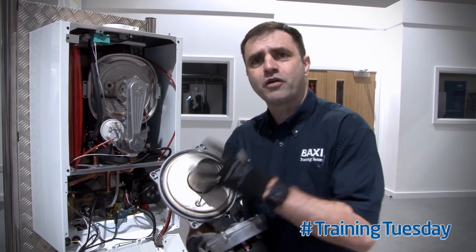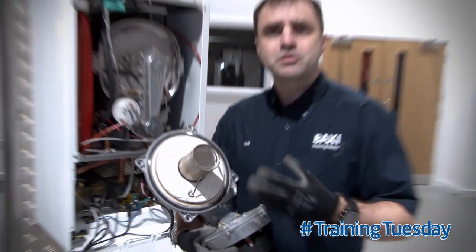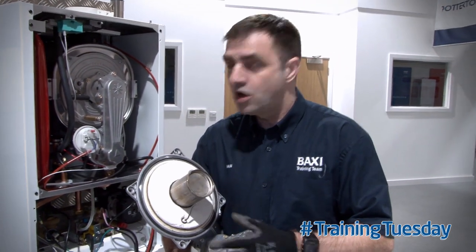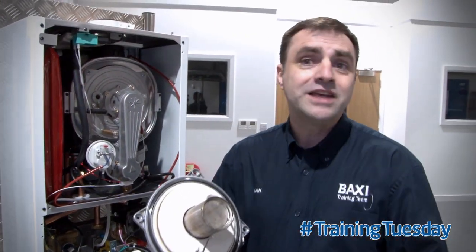So once we remove the burner from the heat exchanger, I want to check around the area and check the seal for any physical damage. Some appliances will state that you have to change the seal on every removal. That's not so for the Baxi Platinum and Duo-tec range. All you have to do is inspect, make sure it's nice and spongy, make sure it's not going white and powdery which indicates signs of heat damage.